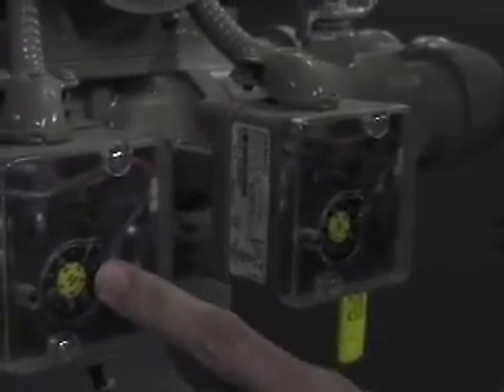Here are your gas pressure switches. You've got your low and your high. This is your low, and this is your high. These have been set around the range that's labeled on your boiler nameplate. It says on there what the inlet gas supply pressure should be between your minimum and maximum, so that's what this is set to. It's not always the same per boiler. Sometimes there are a few inches of water column difference. So if you notice a difference, just check the nameplate on the boiler, make sure that it's in the range that it should be.